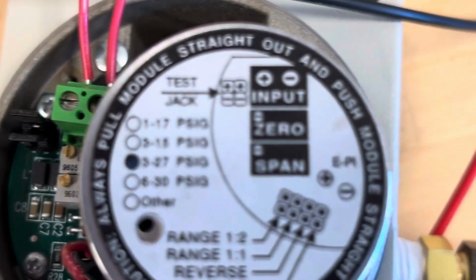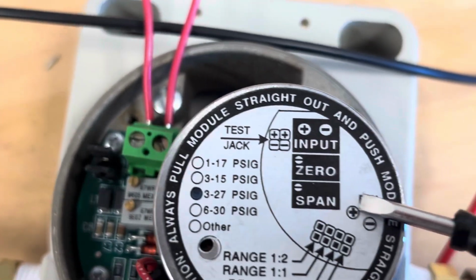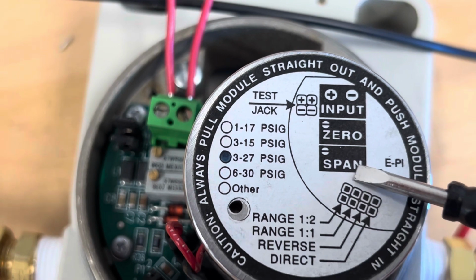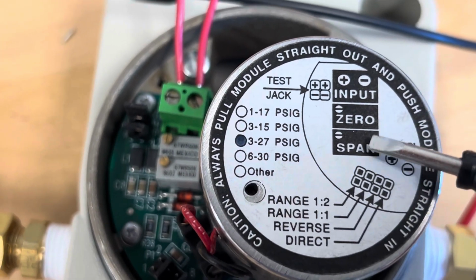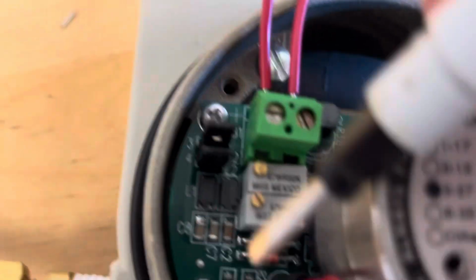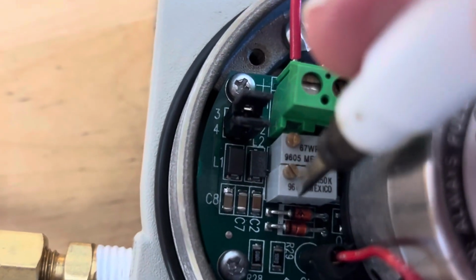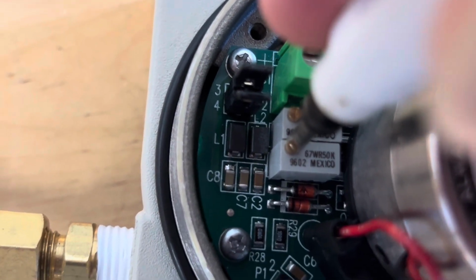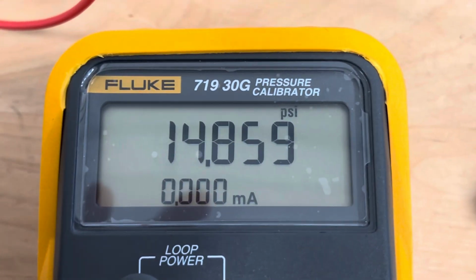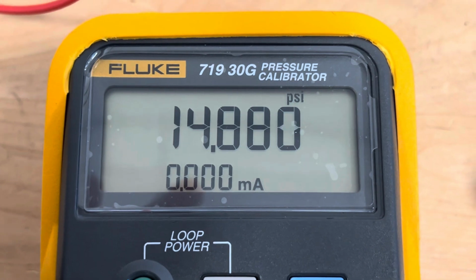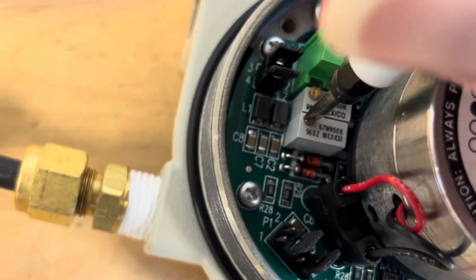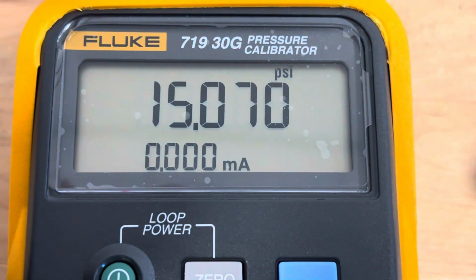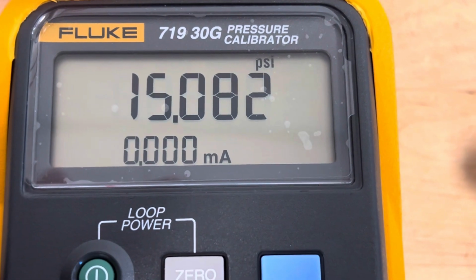So I look here and I see that, what this little menu here is telling me is that my bottom potentiometer is my span, which is the top of my range, 3 to 15 PSI. So this will be for 15 PSI. And I look at the resistor here and I get my screwdriver into the slot on this little screw. All right, now I'm going to go clockwise because that increases. I'm slowly turning this screw, as you see here. As I turn this screw, it increases this number. All right, so we're at 15.0.